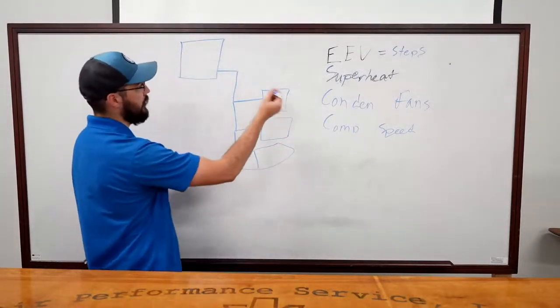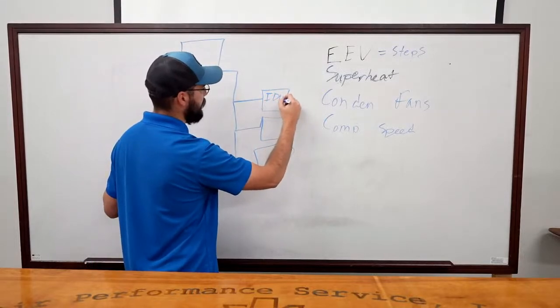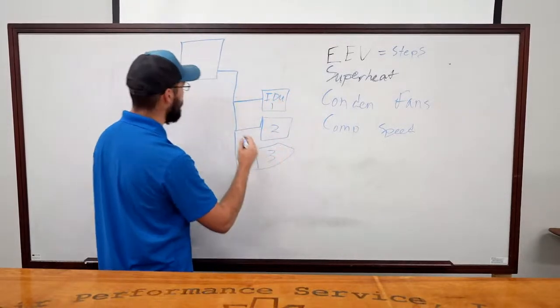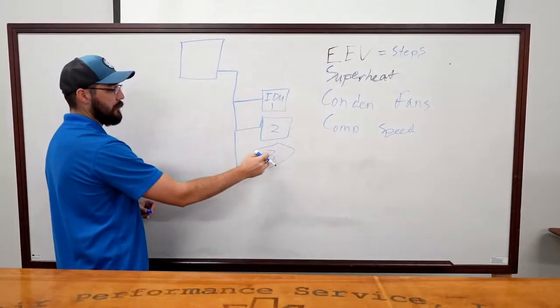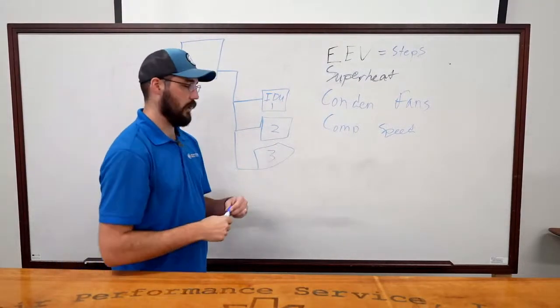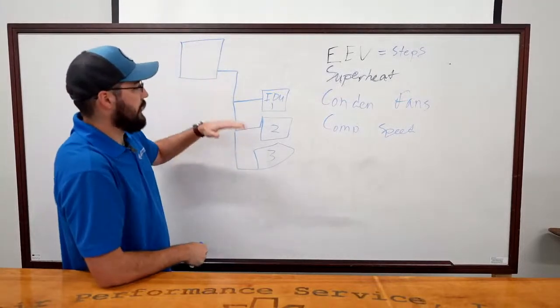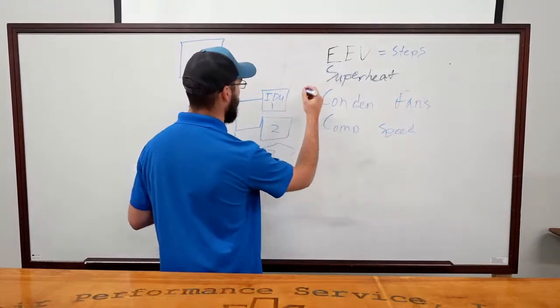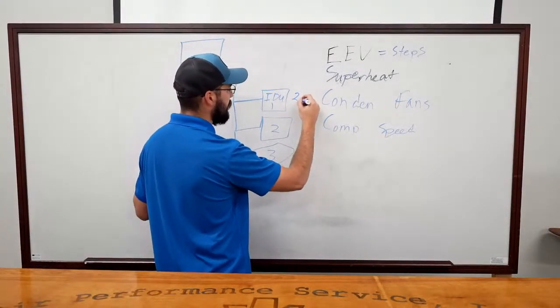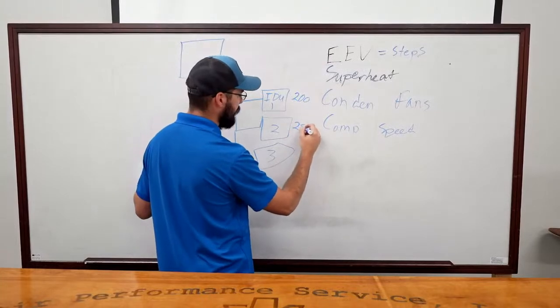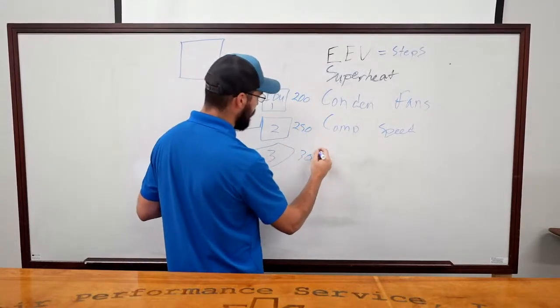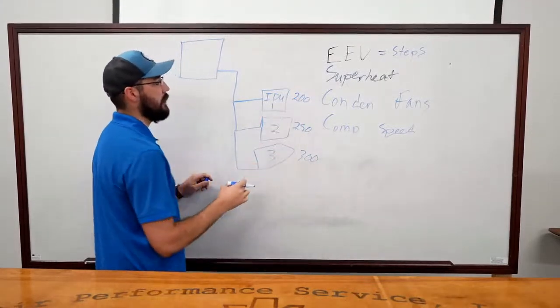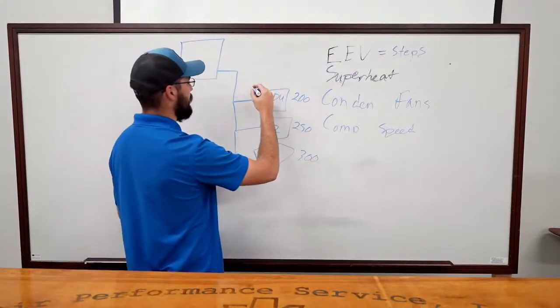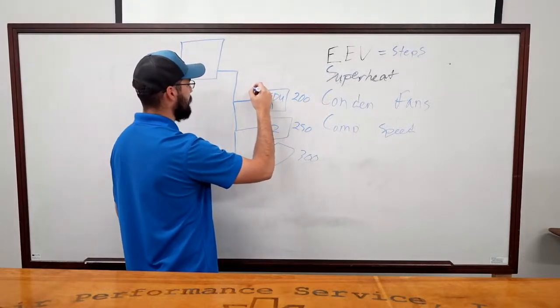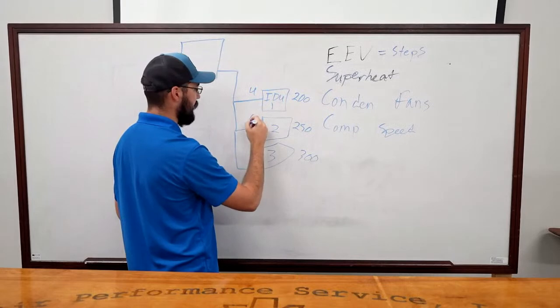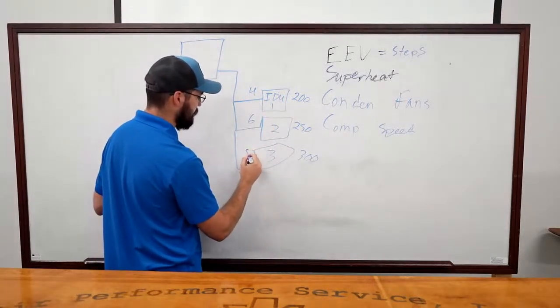My wonderful drawings. Okay, so this is our IDU 1, 2, and 3. Number 3 is the one that's going to show you the most problems first. When you first start these things up, at startup they're all running about 200 steps, 250 steps, say 300 steps. Okay, this is the EEV positions. So they're all running the relative steps, and let's say we're able to maintain, say, 4 degrees of superheat here, 6 degrees here, and this one's maybe 8 degrees.